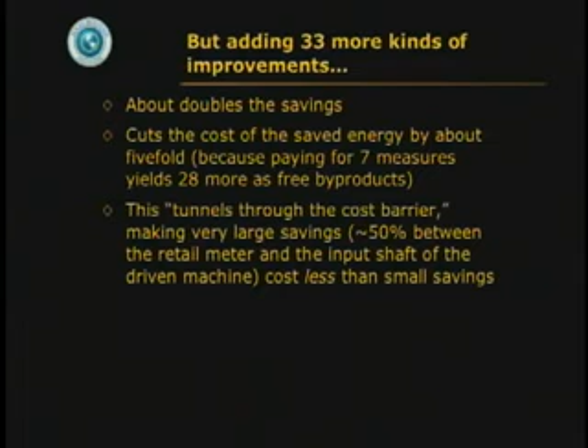By the way, this red X is 14 motors. This red X way down in the basement is 37 motors. Sorry about that, 40 horsepower each. So the gap between best and what we got, assuming the motors are as good as the nameplate says, was worth $1.4 million present value at a 5-cent tariff, and that was only a third of the motors in that one plant. But just making the motors better and adding adjustable speed drives misses 33 other kinds of improvements that about double the savings and cut the cost by about 5-fold, tunneling through the cost barrier.